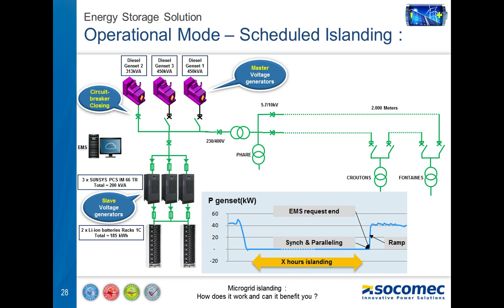When these three parameters are completely aligned, the controller gives the authorization to close the circuit breaker of the genset. And then the microgrid is again in parallel between the genset and the energy storage. At this moment, the energy storage system switches back from master generator to slave generator, and the genset recovers the master voltage generator mode.